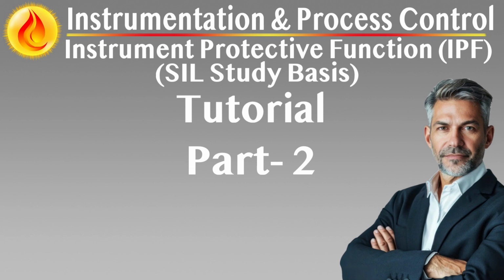Severity classification for personnel safety. Consequence severity to human health is typically classified into defined tiers, ensuring that SIL assessments follow a consistent and traceable standard. Negligible: no injury or health effect. Example: non-toxic release, low temperature steam vent, no exposure risk. Minor: reversible health impact, first aid treatment sufficient. Example: brief exposure to low-level irritants or noise beyond comfort threshold.